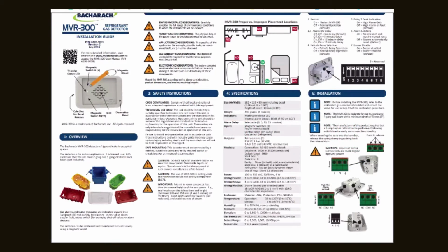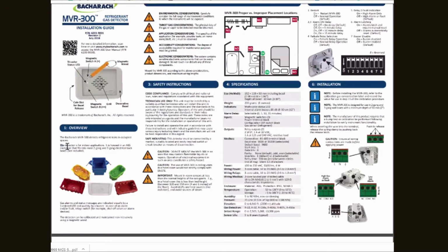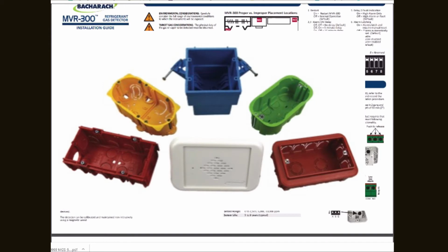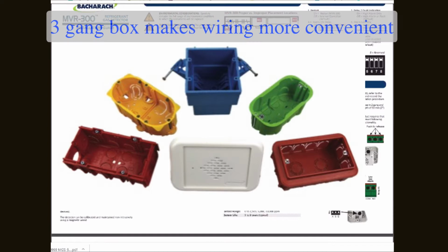One of the things that I want to address right up front, and in fact, we want to highlight here, is that we do suggest that these can be put in a 2-gang or a 3-gang electrical box. We are going to restate that language from here forward and say it's going to be a 3-gang box. Now, these things can go in a 2-gang box, but it's really tight, and it's just an easier install for everybody if it's a 3-gang box. So I want to put that on the table right now. We will be going back and changing all of our documentation in the very near future to address the 3-gang only.